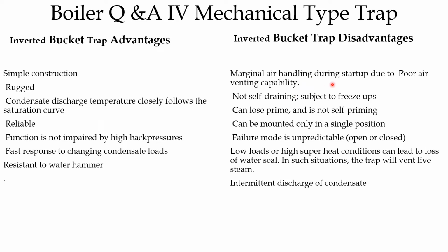Marginal air handling during startup due to poor air venting capability is one of the main disadvantages. So it will delay the trap lining up condition at the beginning. It's not self-draining, subject to freeze ups. Can lose priming and it's not self-priming. Can be mounted only in a single position.